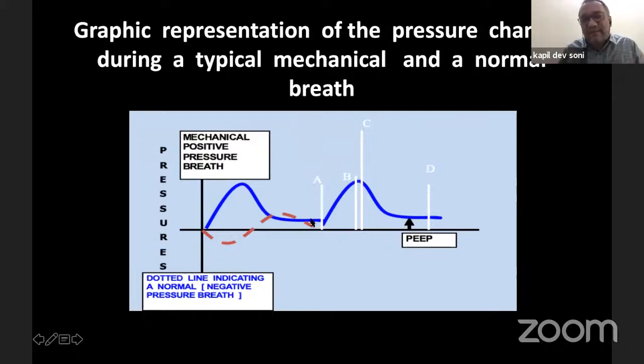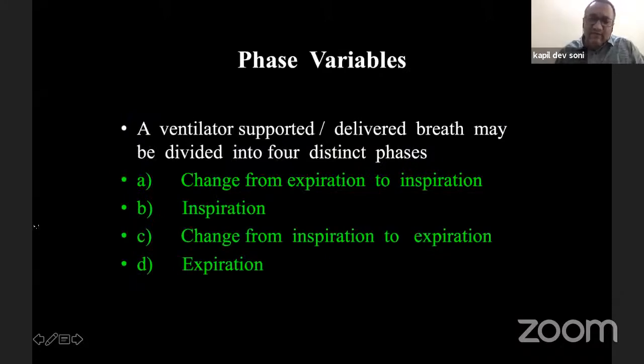So there are multiple phases of a single breath. One is the initiation of the breath, the trigger, then the limit, and then there is cycling. Cycling means change of a phase variable, say from inspiration to expiration. So these are the various phases of a single breath provided by the mechanical ventilator. These are the phase variables. One must be aware how inspiration changes to expiration, what the triggers are, and how the breath is stopped. A change from expiration to inspiration is again determined by these three variables along with time, that is the flow, volume, and the pressure. The inspiratory phase, the change from inspiration to expiration, and finally again the expiration. So these are the four distinct phases of a single breath.